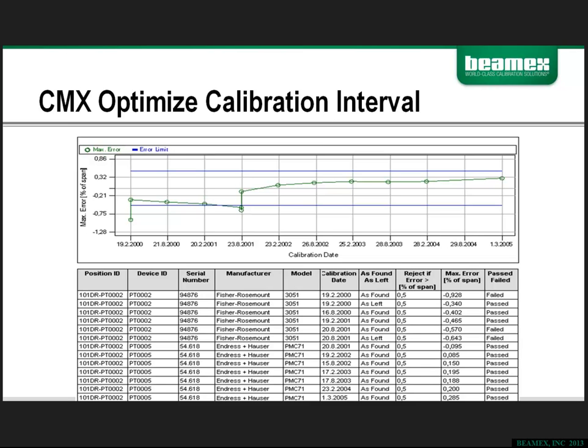So in this particular example, this analysis worked both for tracking underperforming instruments in the case of the Fisher-Rosemount 3051, and those that overperformed in the same position, meaning the Endress+Hauser, which was his justification for modifying his calibration interval and increasing that interval from 6 months to 12 months, just eliminating the need for calibrating this instrument more than once a year. So by this example, you can see that there was a time savings.